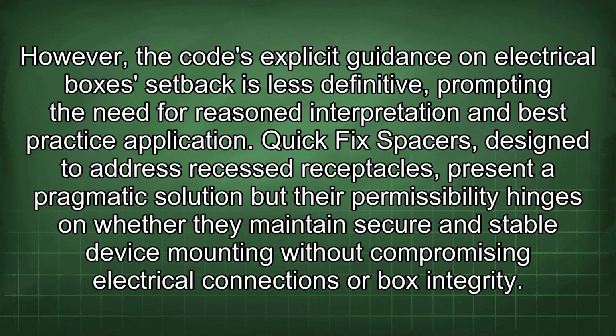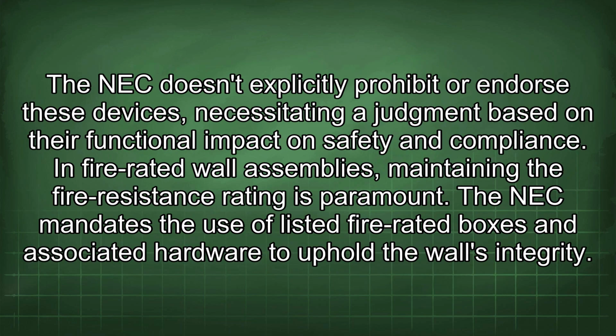However, the Code's explicit guidance on electrical boxes setback is less definitive, prompting the need for reasoned interpretation and best practice application. Quick-fix spacers, designed to address recessed receptacles, present a pragmatic solution, but their permissibility hinges on whether they maintain secure and stable device mounting without compromising the electrical connections or box integrity. The NEC doesn't explicitly prohibit or endorse these devices, necessitating a judgment based on their functional impact on safety and compliance. In fire-rated wall assemblies, maintaining the fire resistance rating is paramount.